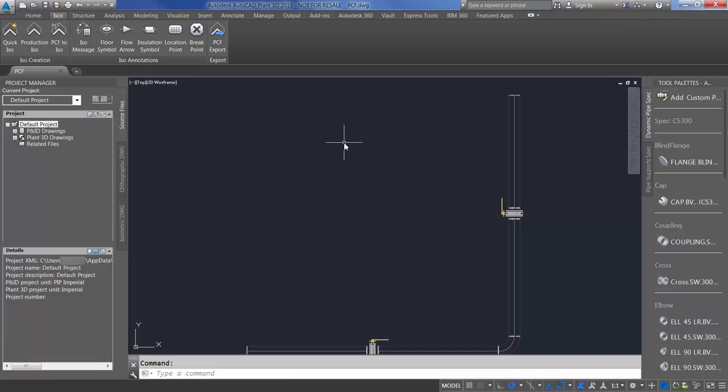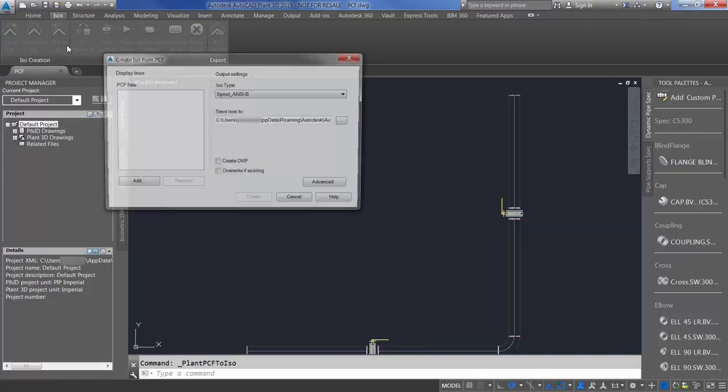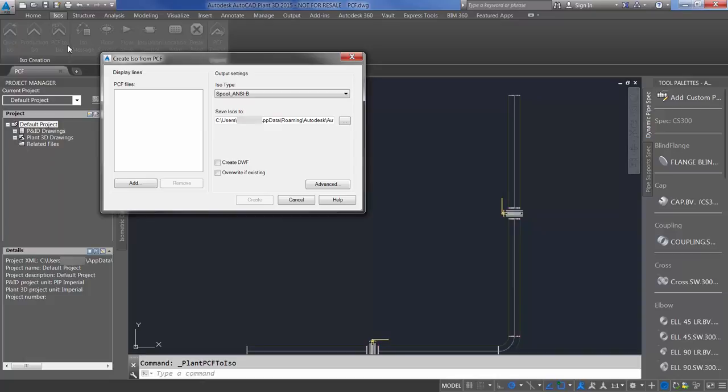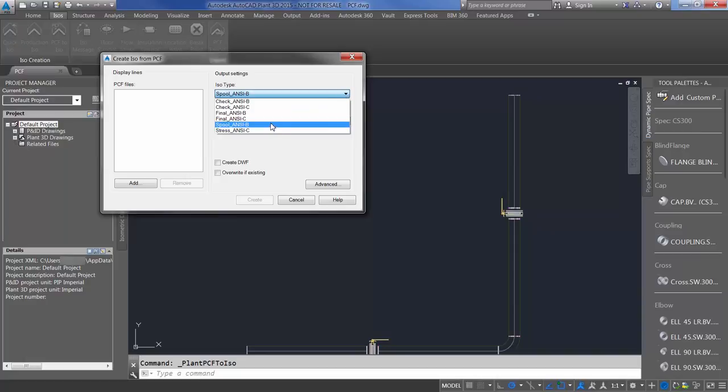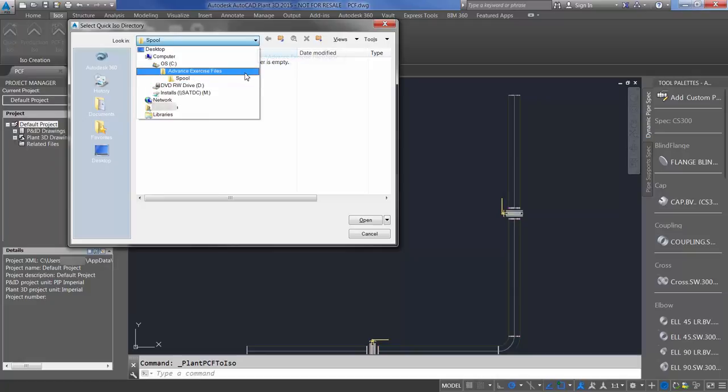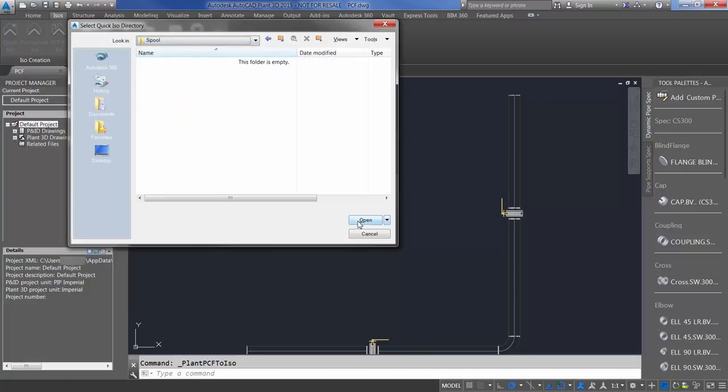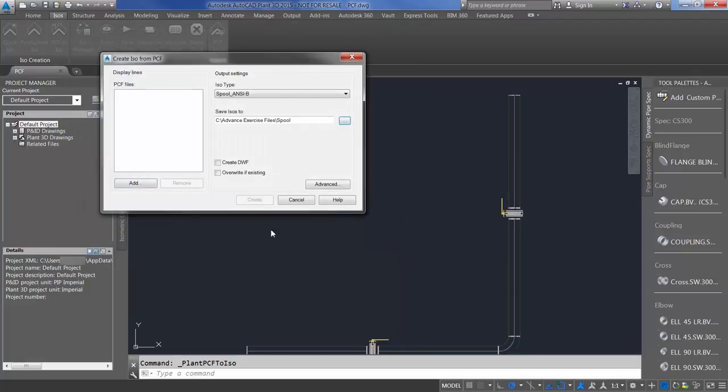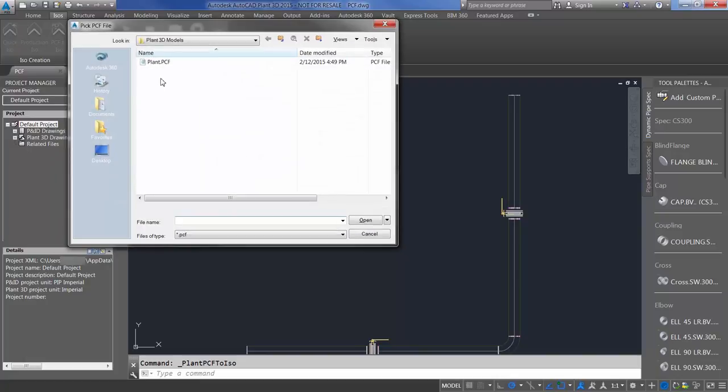I've opened up Plant 3D and I've brought the drawing in. At this time, I need to select PCF to ISO in the Create ISO from PCF dialog. Here I have the ability to create my different ISO types. I'm going to select Spool ANSI-B. I'm going to select my Save Location. I'm going to save this to Advanced, Exercise Files, Spool. Select Open. The last thing I need to do is add the PCF file that I created inside of CAD MEP.